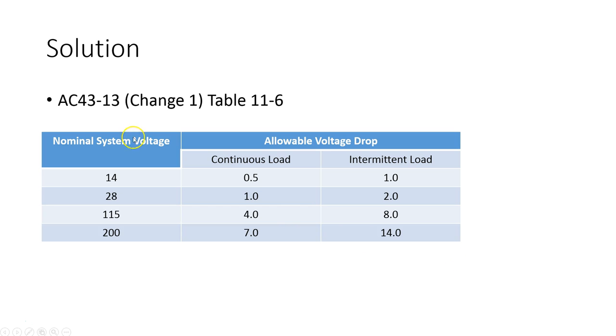So if we refer to advisory circular 4313 we will see in table 11.6 that I have a 28V system and I have continuous load. Then the allowed voltage drop is 1V.